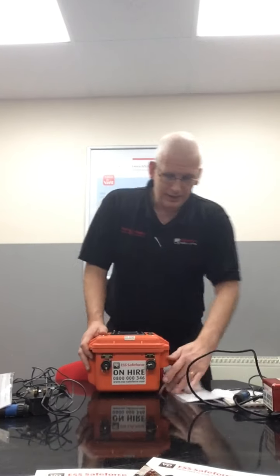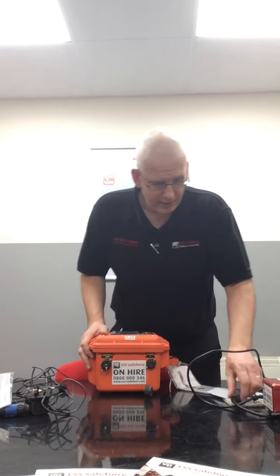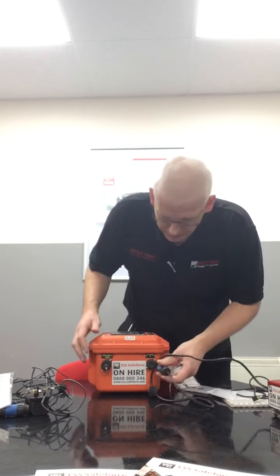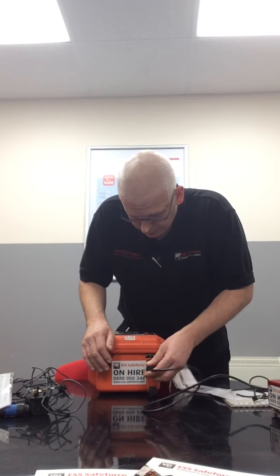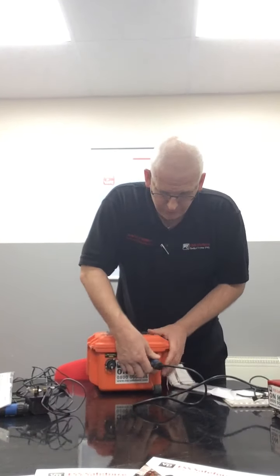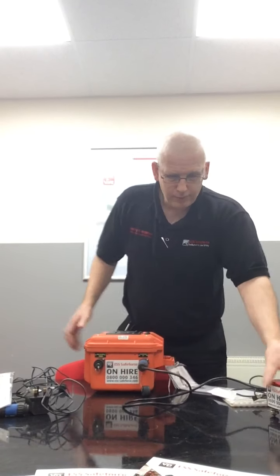The next stage of your setup process is to connect the transducer to the unit itself. So you would undo it there, take your transducer, line it up, and then hand tighten the transducer onto there. Then you'd take it onto site wherever you're going to get this set up, and set it up on a firm surface on the perimeter of your site, so that it can take all the readings and the vibrations that are coming through. That's basically how you'd set one up.